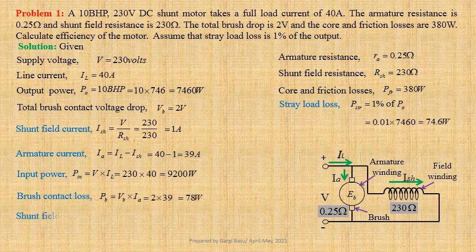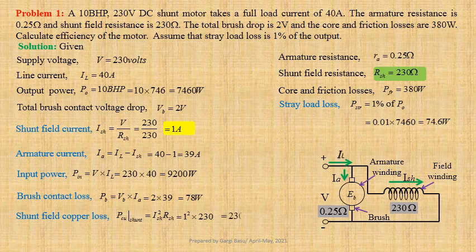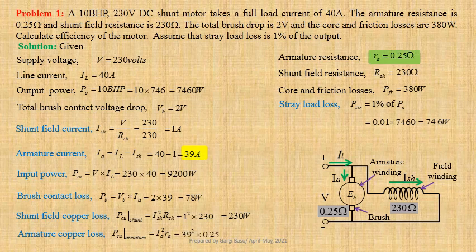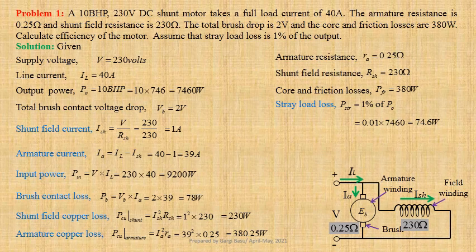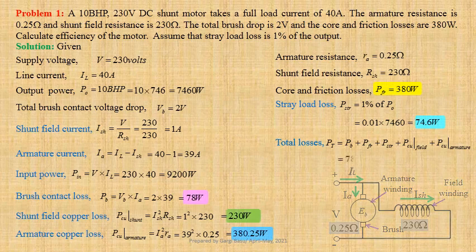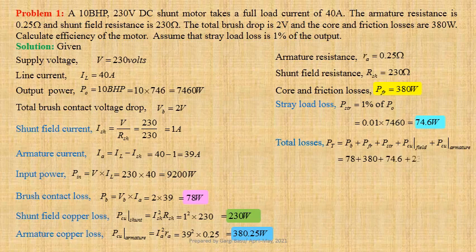Shunt field copper loss: P_copper_shunt equals ISH² times RSH, that is 1² times 230, giving us 230W. Armature copper loss: P_copper_armature equals IA² times RA, that is 39² times 0.25, giving us 380.25W. Total losses PT equals PB plus PFR plus PSTR plus P_copper_field plus P_copper_armature. Using values: 78 plus 380 plus 74.6 plus 230 plus 380.25, giving us 1142.85W.